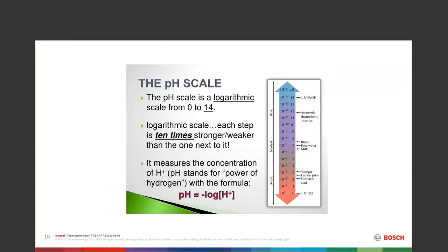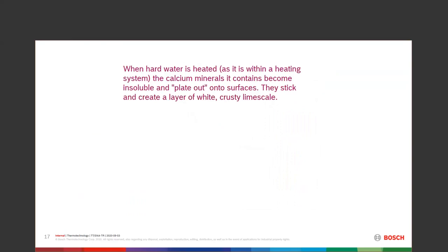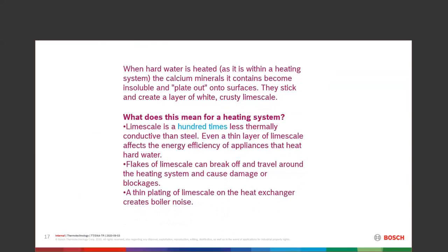Hard water contains calcium and magnesium. When heated — usually around 130–140°F — those minerals come out of suspension and turn into solids that stick to the hottest surfaces inside the boiler, forming a white crusty layer of limescale. That scale is a hundred times less thermally conductive than steel, so even a very thin layer starts messing with efficiency — how well can we transfer the heat from the fire side through the metal and into the water?